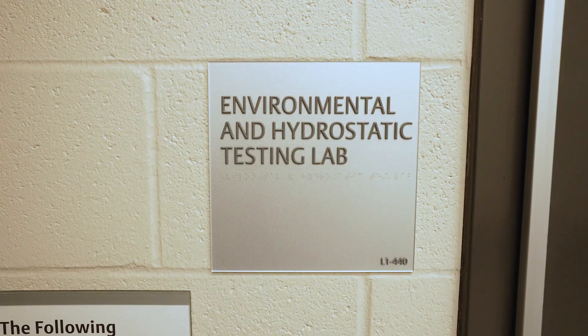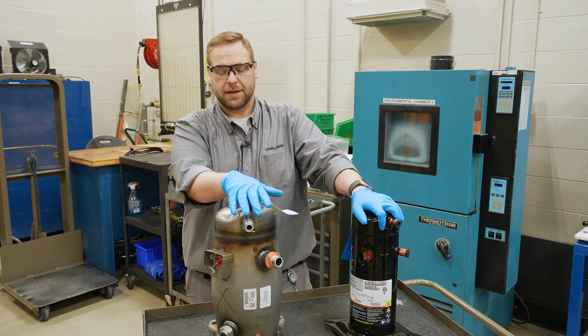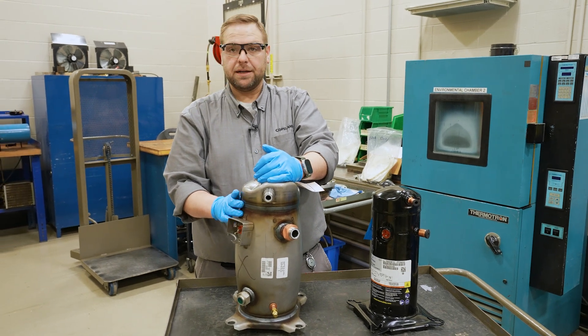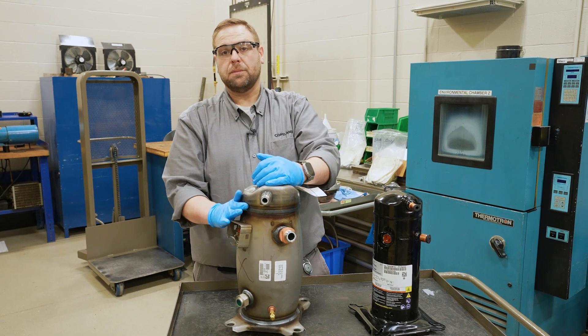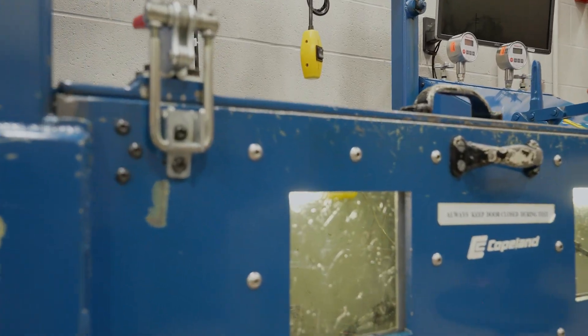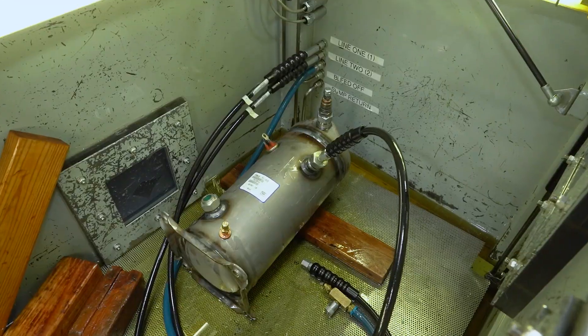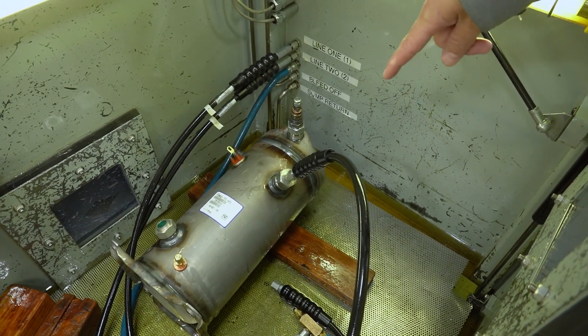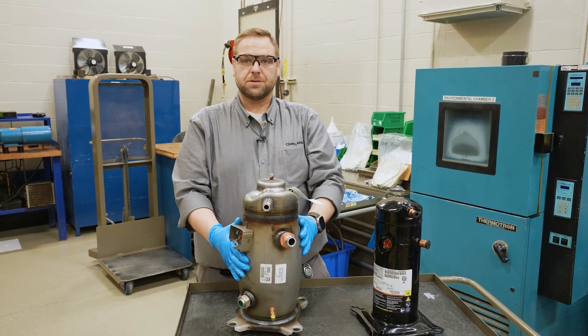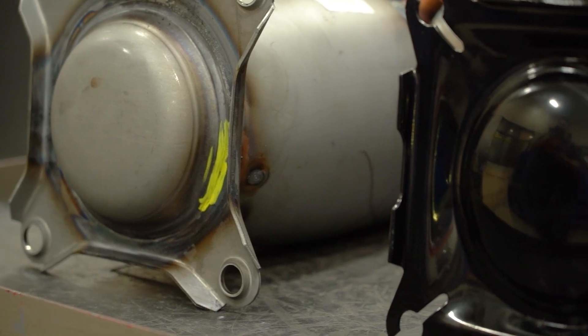What I have here is a comparison of what a compressor looks like before hydrostatic testing and what it could look like afterwards. We test the shell and the welds on it for integrity — to make sure they hold up to the pressure we require, and that UL labs require. We lay the compressor on its side inside a hydrostatic tank with bulletproof glass, pump hydraulic fluid in, and pressurize it to above 2,000 PSI. You can actually see where the stress fracture and failure occurred right here along this bottom weld, in comparison to one that hasn't been tested yet.